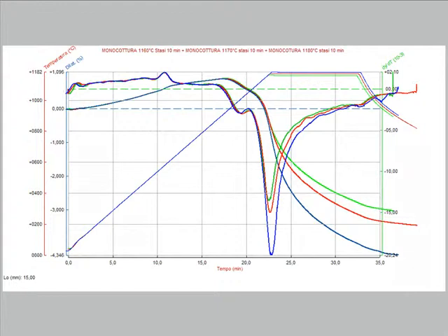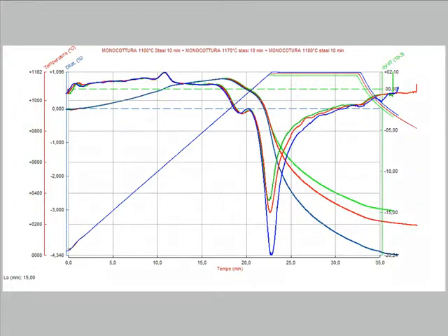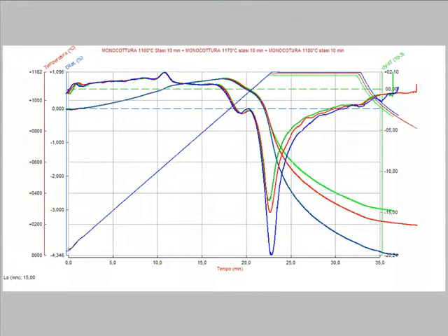The optical dilatometer MISURA-HT allows the study of the kinetics of sintering as a function of temperature or as a function of time. This graph shows three sintering tests at different temperatures with the first derivative of sintering or sintering speed and the heat treatment. A different color is assigned to each test for all the curves: the sintering curve, the speed of sintering, and the temperature. These tests show that the shrinkage increases as the temperature increases and it grows with time at constant temperature.